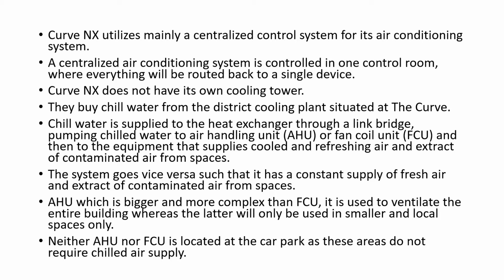Chilled water is supplied to the heat exchanger through a link bridge, pumping chilled water to the air handling unit, AHU room, or fan coil unit, FCU, and then to the equipment that supplies cool and refreshing air and extracts contaminated air from spaces. So the system goes vice versa, such that it has a constant supply of fresh air and extract of contaminated air from spaces. AHU, which is bigger and more complex than FCU, is used to ventilate the entire building, whereas the latter is only used in smaller, local spaces. Neither AHU nor FCU is located at the car park, as these areas do not require chilled air supply.